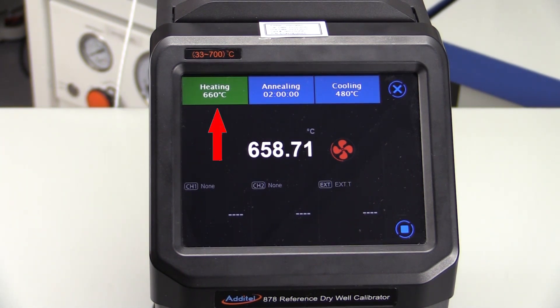Then the 878 will automatically move to an annealing countdown. In this case, the calibrator will anneal for two hours.